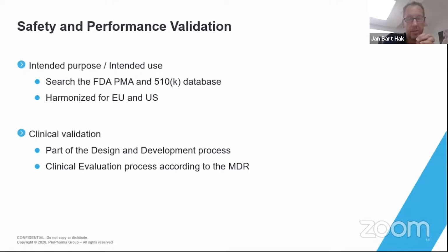And not only that, you can also find the summary of the 510K or PMA. And that includes, for instance, the intended purpose, intended use statements. So as an example, if you start to design for Europe, but also have plans to go into the US, it may pay off to search those databases and see what alternative similar devices are claiming, what their intended use is, and perhaps you could copy that intended purpose.